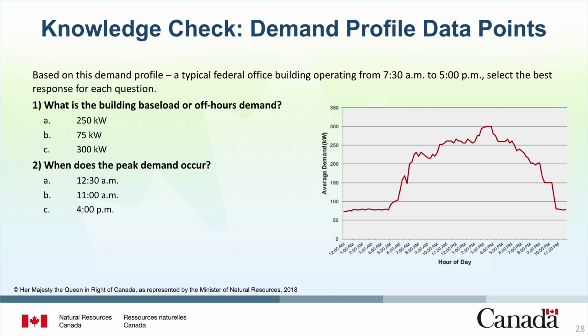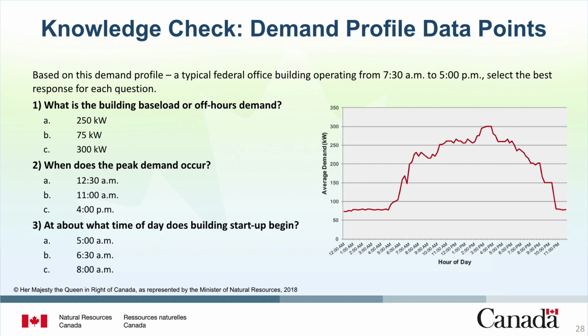Question 2. When does the peak demand occur? And finally, question 3. At about what time of day does building startup begin? The answer to question 1 is 75 kilowatts. The baseline is the low load that occurs over the 24-hour operating periods.